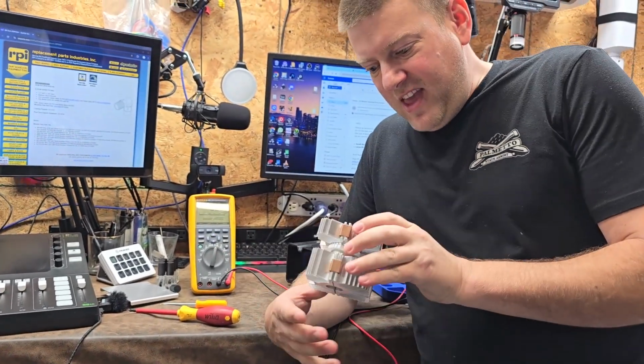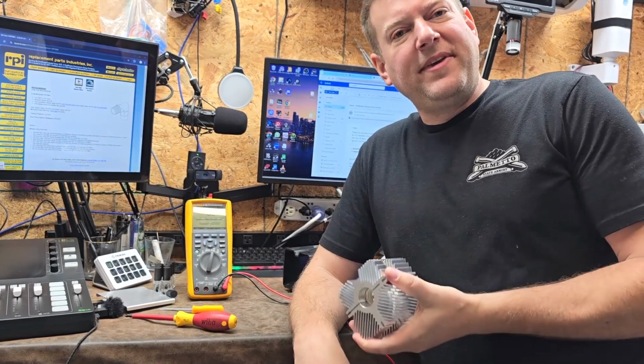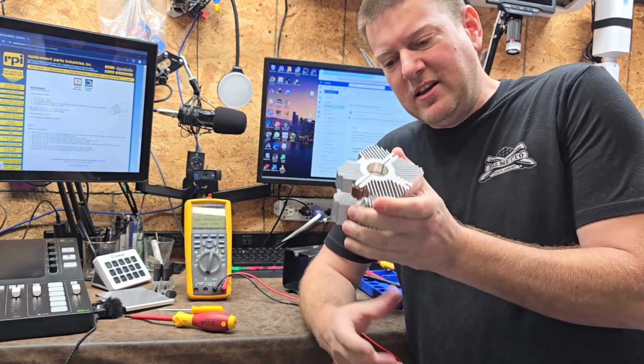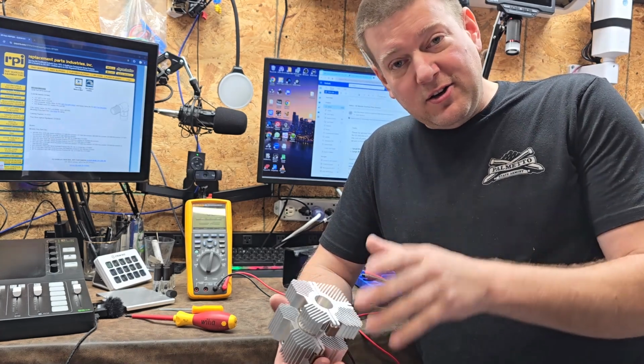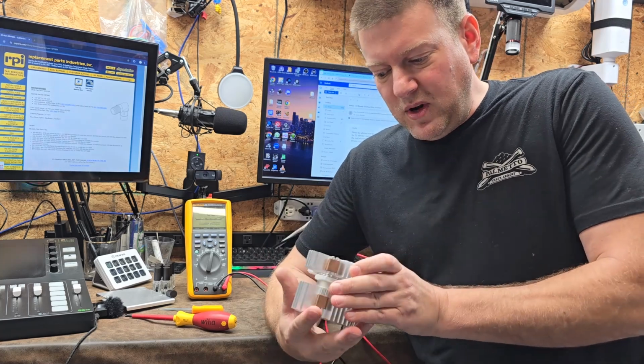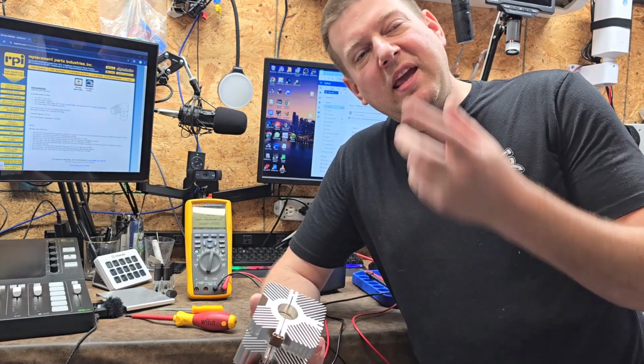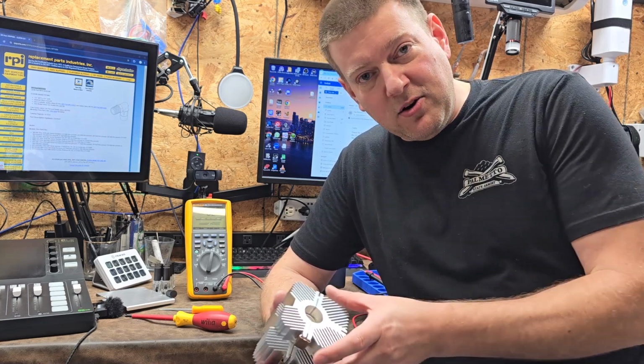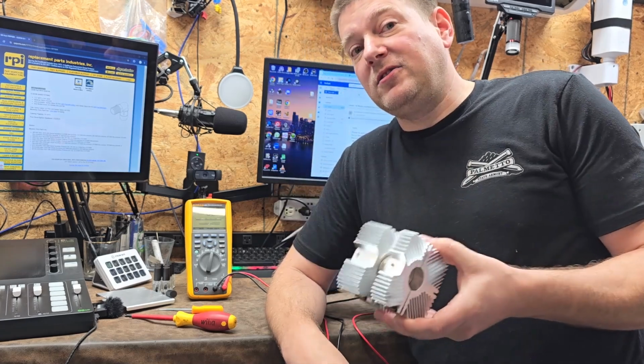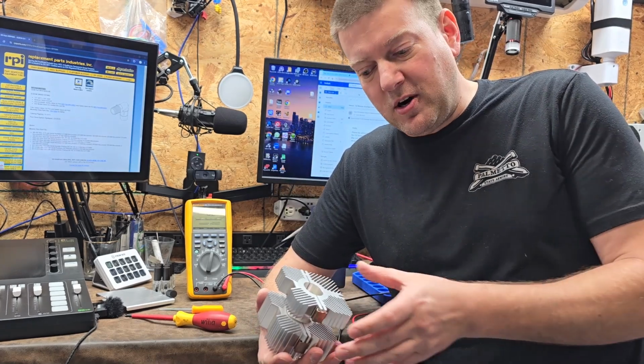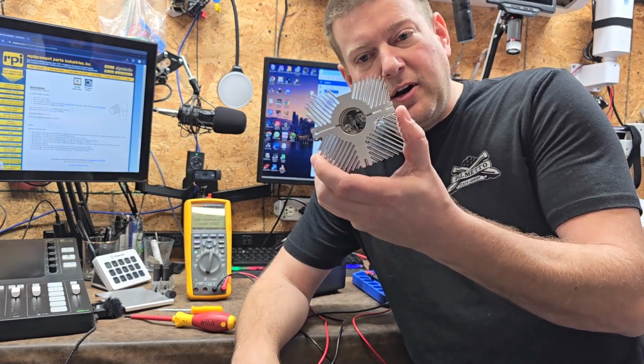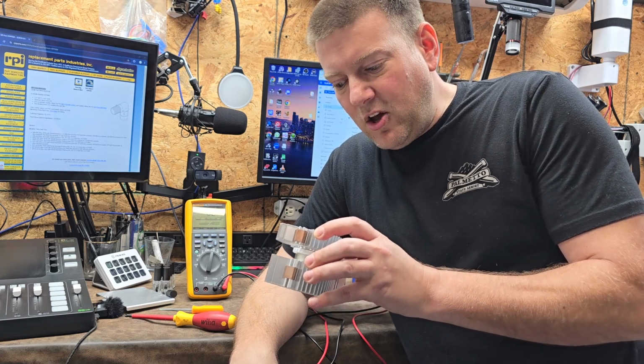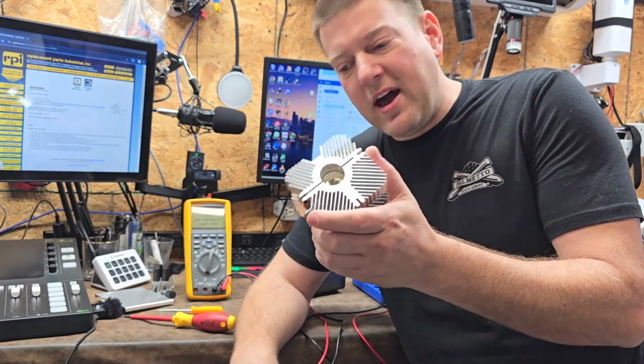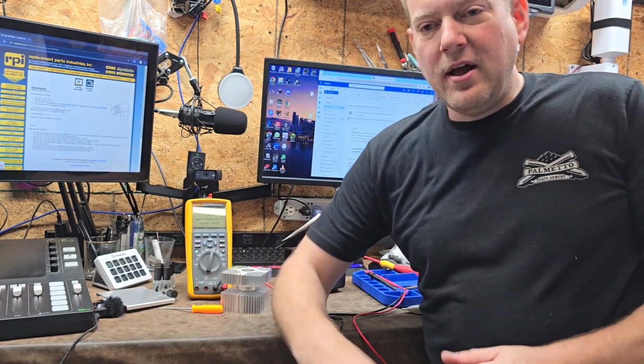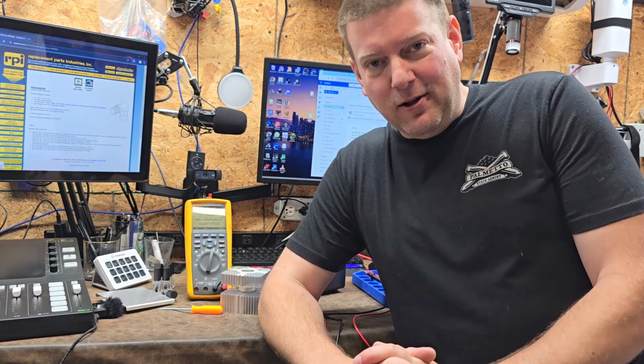Anyway guys, that's a quick step-by-step troubleshooting of a Xenon light source. Can't say I've ever really seen a problem like that, like a bulb creating the issue. Now I'm not saying the bulb is the entire issue — it's going to get a replacement Xenon bulb, and once we get the replacement, we're going to test that power supply under load again. It's possible there's a component failing on the power supply, and once you put any sort of load on it, it starts internally arcing and popping the fuse, drawing too much current. But because I can see the dark arcy spark on that parabolic reflector, that's telling me there's an electrode that's way too close, or this bulb is way out of spec, and that's drawing too much current from the power supply, and that's why it's popping the 6.3 amp fuse. It's a tiny little fuse, and there's not too much to go for.